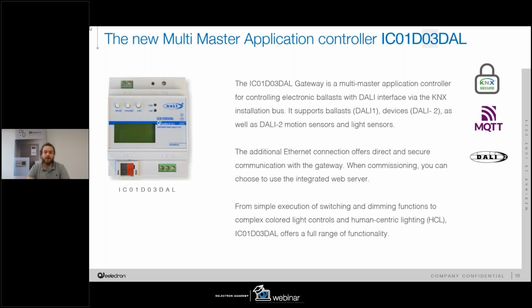In addition, the IP port gives you the opportunity to have a web page. Inside there is an integrated web server, a very easy web server that is not a supervision for your entire KNX system, but is a supervision for your DALI system over a single gateway. So this means that if you have two different gateways, you will have two different IPs to point to and access each web server. With the web page, you can also control your DALI gateway, have diagnostics, and also get some reports for the emergency lighting system, as we will see later.